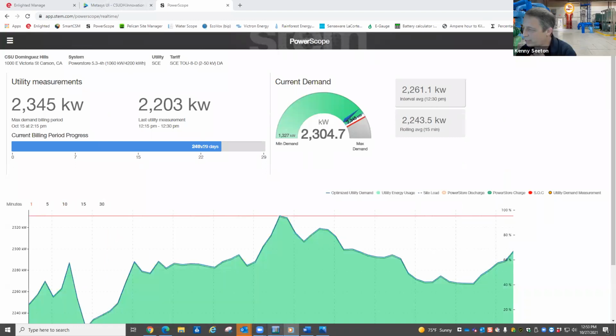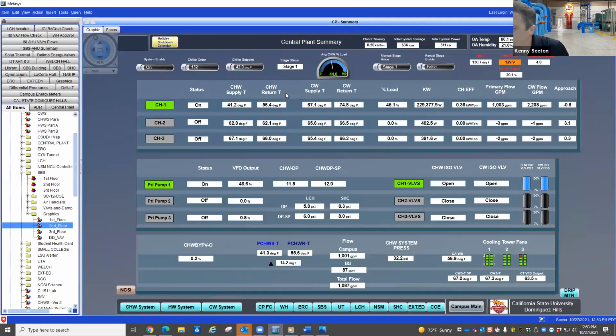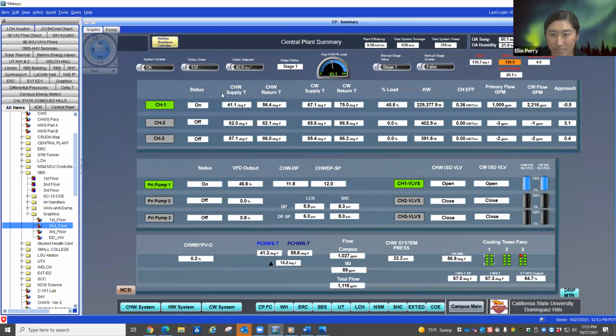So let us just real quick show you some of the stuff that we can see on the buildings. Everything is digitized, everything is brought into the computer so we can see it. This particular screen is showing us that we have 3 chillers. Chiller 1 is the one that's running. It's supplying us with 41-degree water. The return water from the campus is 56 degrees. That's really good. We're doing a 14-degree delta T, the difference between the supply and the return. We have a delta T for air, for water, for different things.